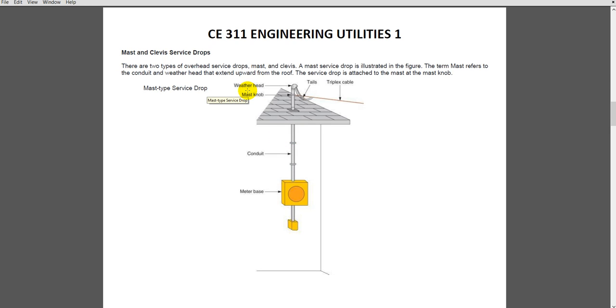So, there are two types of overhead service drops: mast and clevis. A mast service drop is illustrated in the figure. The term mast refers to the conduit and weatherhead that extend upward from the roof. The service drop is attached to the mast at the mast knob. So this is our mast type service drop. The significant difference with the mast service drop is that it sits above the roof.